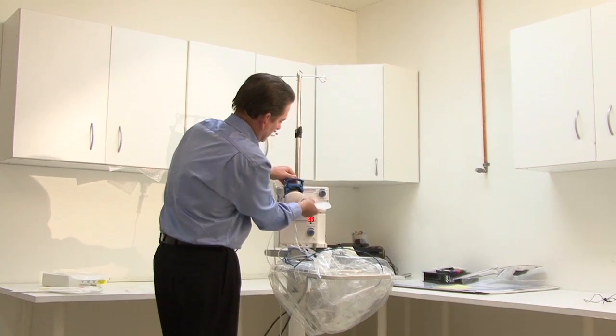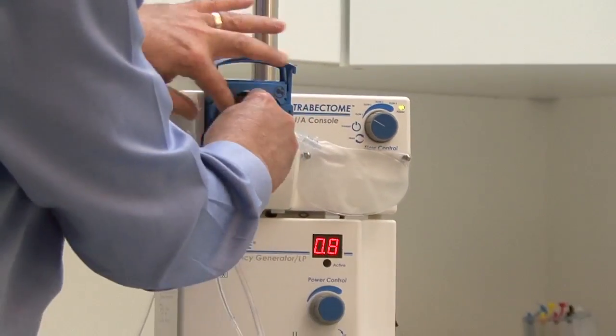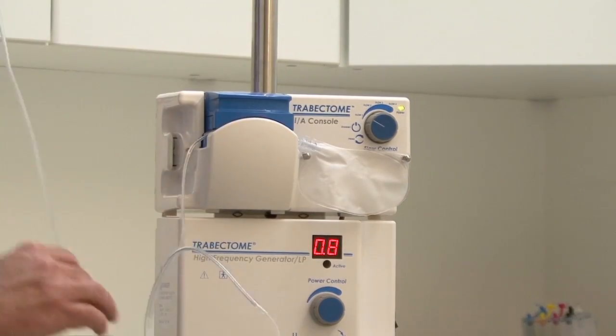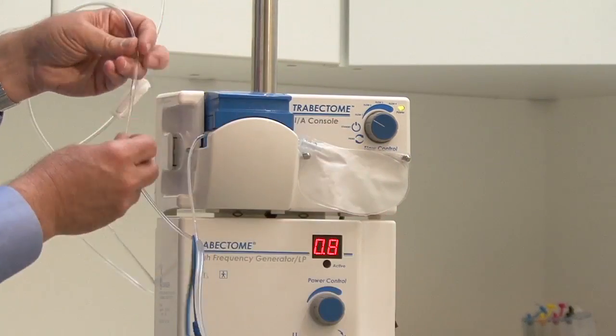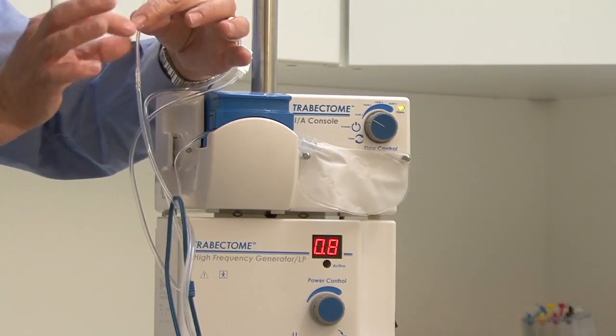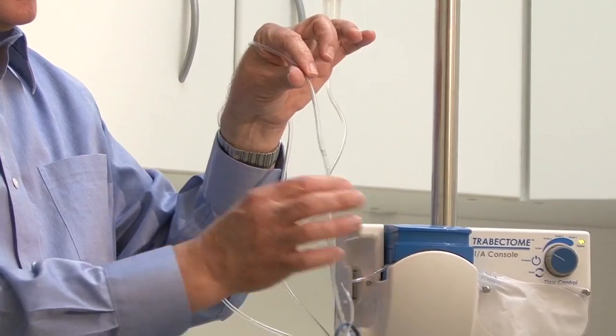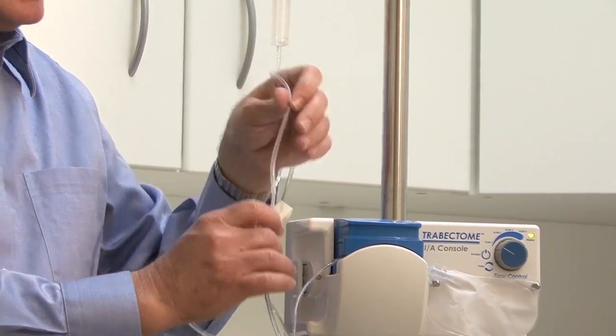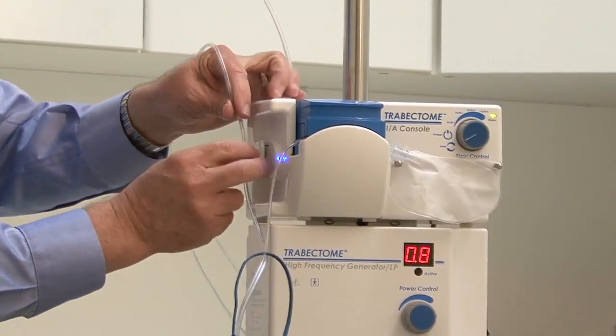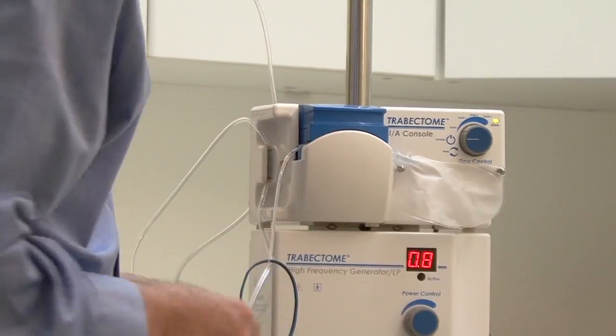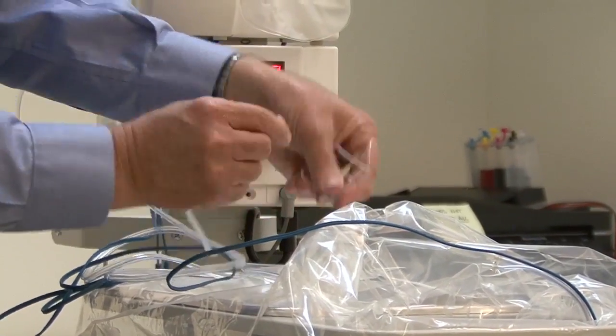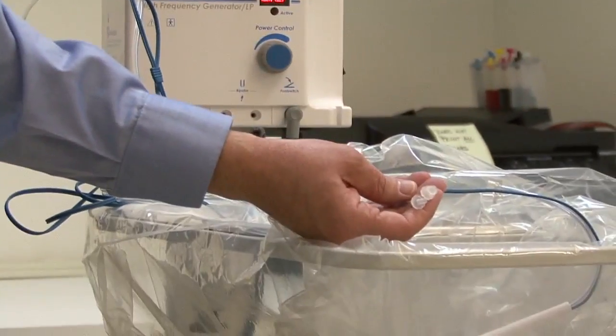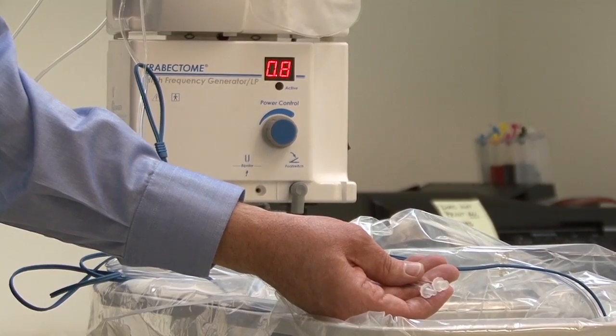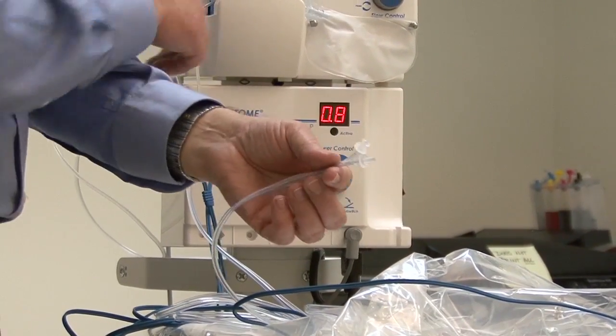And the most common setup problem is just not getting that tubing inserted properly into the slot. So what happens is, if it doesn't get in the slot, you can imagine it's just never turning off because it's never being pinched closed. As you recall, what we normally do is we turn on the valve, we pop that tube in, we turn this off after we flush the irrigation line, and then we connect to the handpiece. When we turn this off to connect the handpiece, we should see the fluid stop flowing, the irrigation, if this is properly inserted.